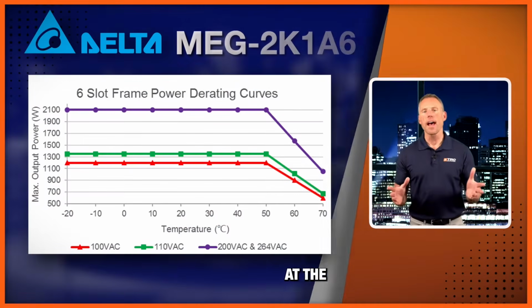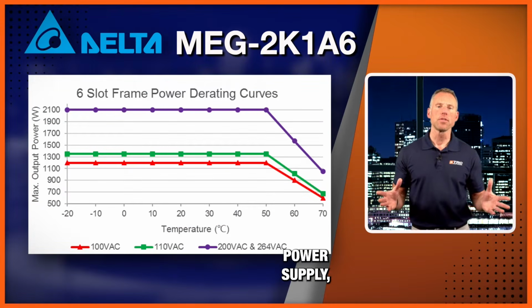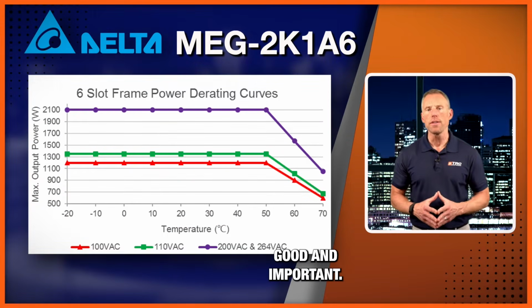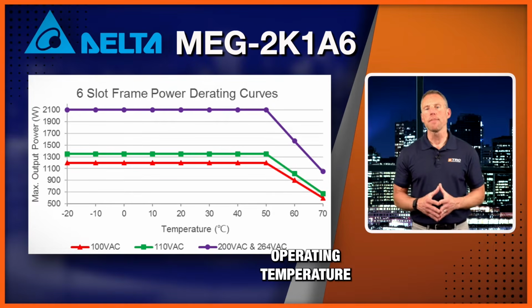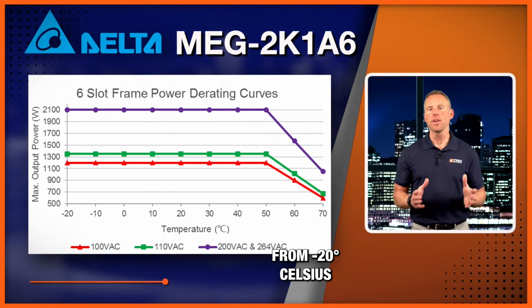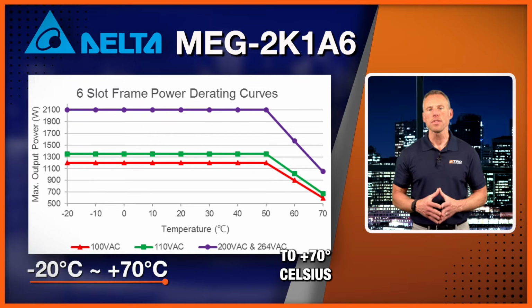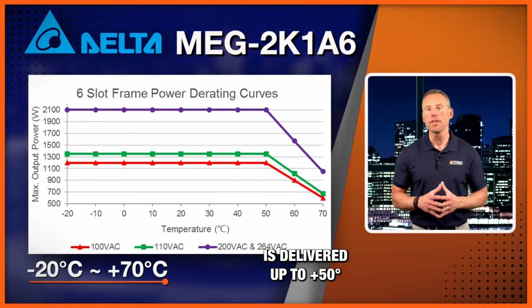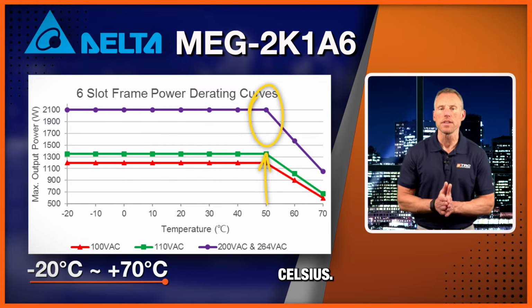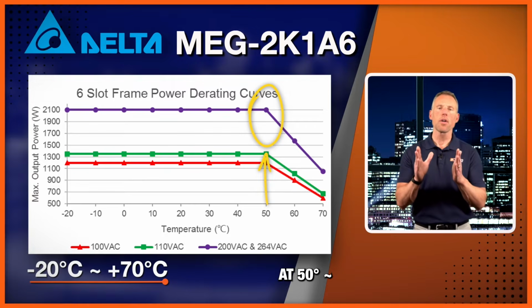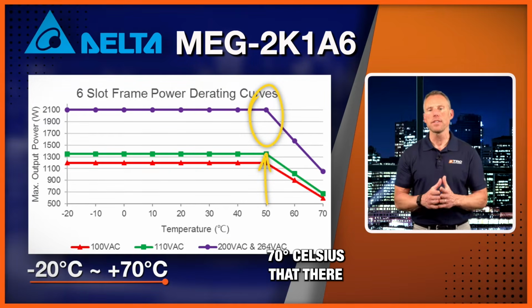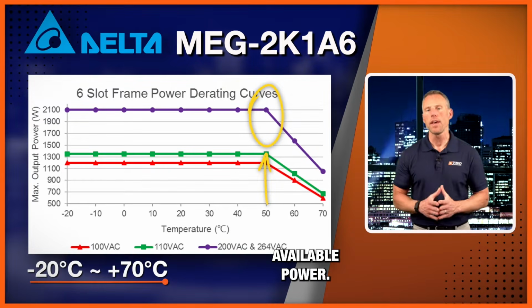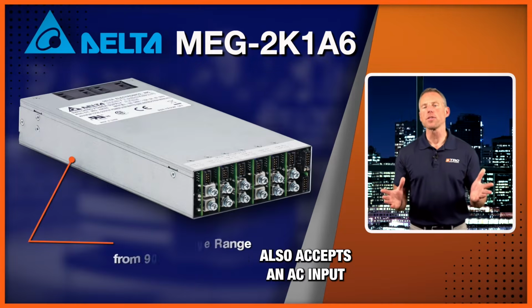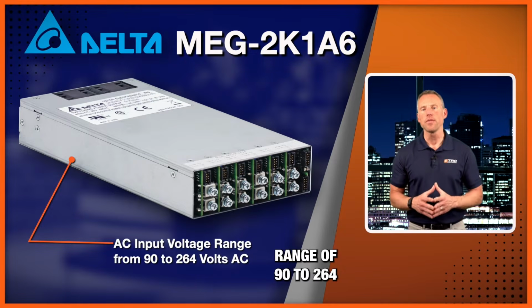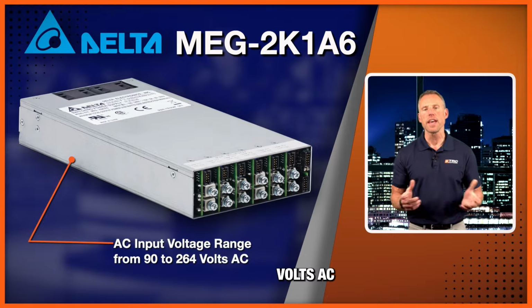Let's also look at the power derating curve of this power supply, because this is really important. You'll notice the operating temperature range is from -20 degrees Celsius to +70 degrees Celsius, and full power is delivered up to +50 degrees Celsius. So be aware that between 50 and 70 degrees Celsius there is some derating in the maximum available power. This power supply also accepts an AC input range of 90 to 264 volts AC.